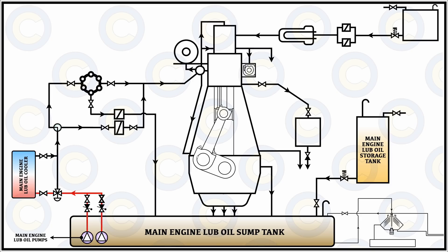The sea water cooled system is more common. After the lube oil has lost the heat gained through its entry into the system and return into the sump tank, the oil moves further. From here it can go to two places: one is the backwash filter and one is the bypass filter. Under normal running conditions, the oil passes through the backwash filter, which can be periodically backwashed automatically or manually. In parallel, oil can also pass through the sludge checker and return to the sump tank. If the filter system pressure becomes low during critical operations, the bypass filter provides the second line through which the oil can pass and join the main line.